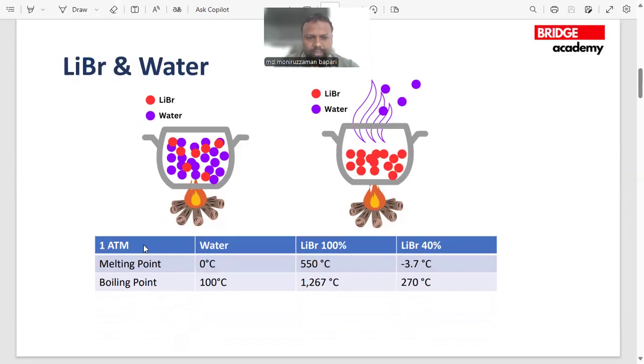Now, at 1 atmospheric pressure, the melting point of water is 0 degrees centigrade, and the boiling point is 100 degrees centigrade. However, when it comes to lithium bromide, if it is 100% pure, the melting point is 550 and boiling point is 1267 degrees centigrade. However, when it comes to lithium bromide 40% solution, lithium bromide is basically a hydrophilic substance. It can absorb water. So melting point is now negative 3.7 degrees centigrade and boiling point is 270 degrees centigrade.